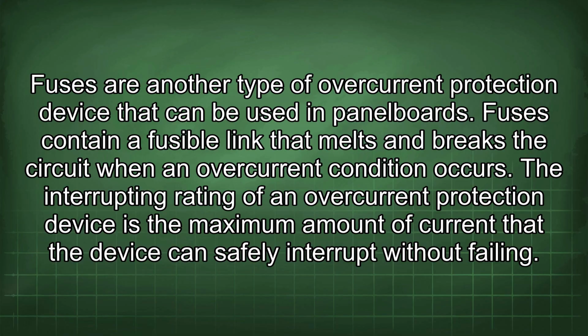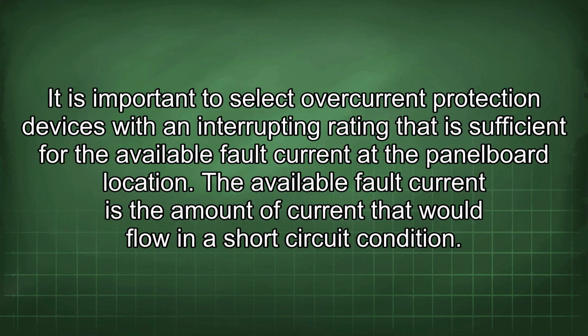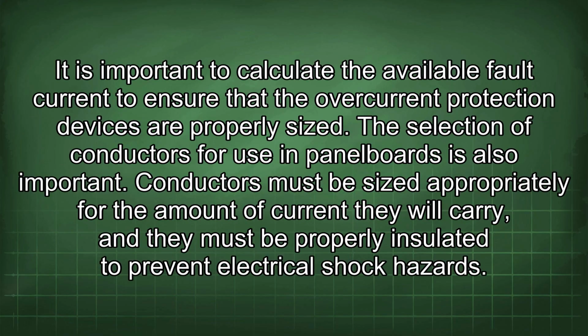The interrupting rating of an overcurrent protection device is the maximum amount of current that the device can safely interrupt without failing. It is important to select overcurrent protection devices with an interrupting rating that is sufficient for the available fault current at the panelboard location. The available fault current is the amount of current that would flow in a short circuit condition. It is important to calculate the available fault current to ensure that the overcurrent protection devices are properly sized.